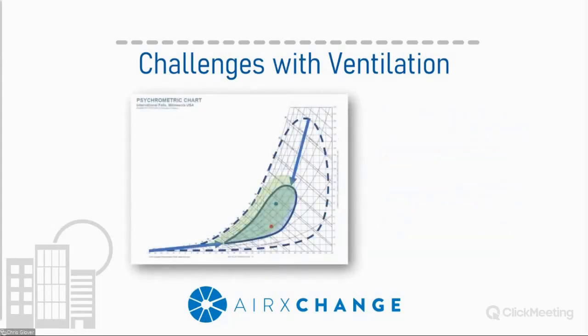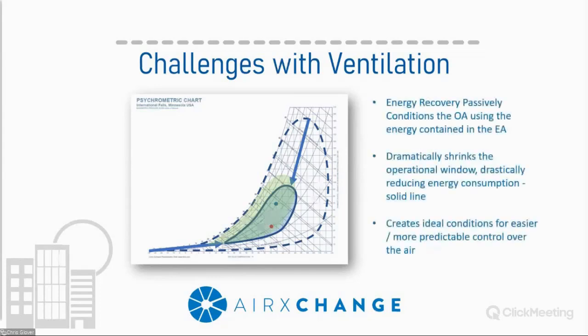So energy recovery has really been developed to respond to those challenges. The easiest way I can describe an energy recovery process is that all this device wants to do all year long is bring the outside air condition as close as it possibly can to the indoor condition. Depending upon how effective that device is determines how close it actually gets. It does this passively, meaning as long as there is a difference in thermal energy or moisture, this device is going to be working to perform that process. Typical energy recovery systems reduce the energy load of the ventilation system, typically between 50 and 80%. You can get higher efficiencies if you design for it, but most common systems are going to reside in that window.